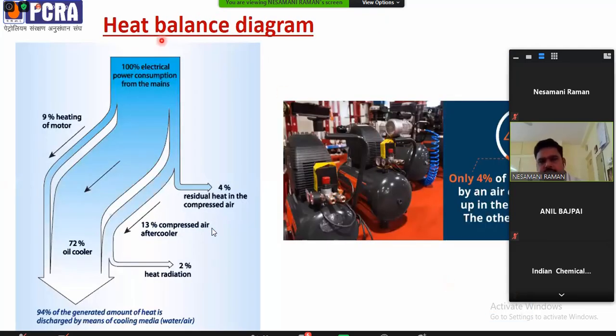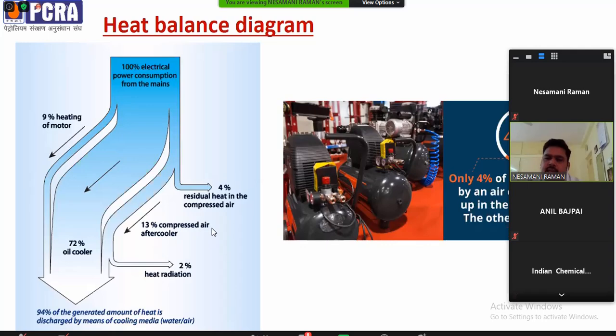This is the heat distribution, the heat balance diagram of the compressed air line. If 100% is given in the form of electrical energy, 9% will be wasted in the form of motor heating, and 72% is carried away by the cooling water or oil cooler. Only 4% of the heat produced by an air compressor ends up in the compressed air. The other 96% is being wasted at present.